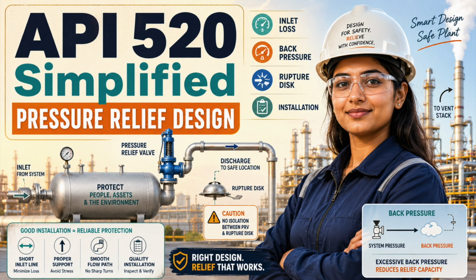You also need to control the pressure language, because pressure relief design becomes confused when operating pressure, design pressure, maximum allowable working pressure, set pressure, overpressure, accumulation, and relieving pressure are treated as interchangeable values. Maximum operating pressure belongs to normal operation. Design pressure belongs to the mechanical design basis.